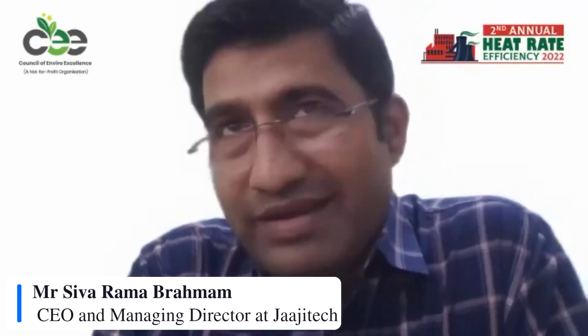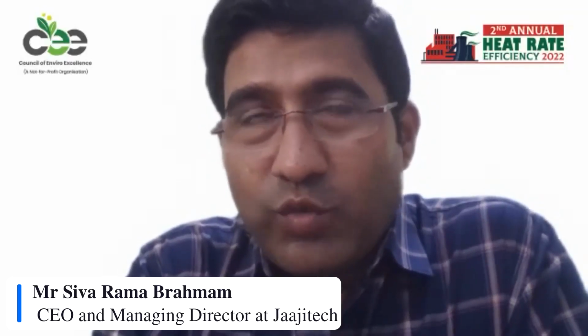For the optimization part, we are right now doing DVR, data validation, reconciliation, and the optimization in Excel, and then taking the data back into our system and providing all the visualizations required. Whatever we did in Mexico is a 100% online system, taking data from the DCS using the OPC interface, and doing real-time coefficient calculations, rated calculations, and corrected calculations, and giving the KPI drill-down to find out what the issue is, with anomaly detection, alerts and notifications.